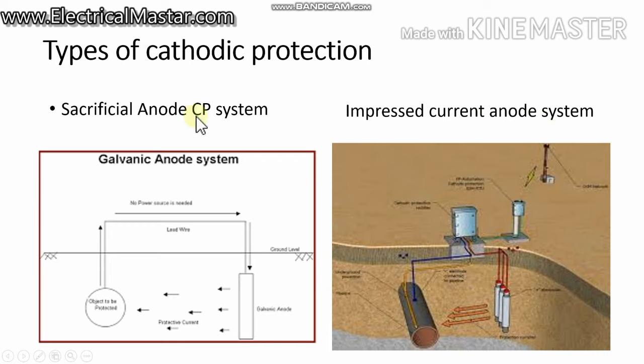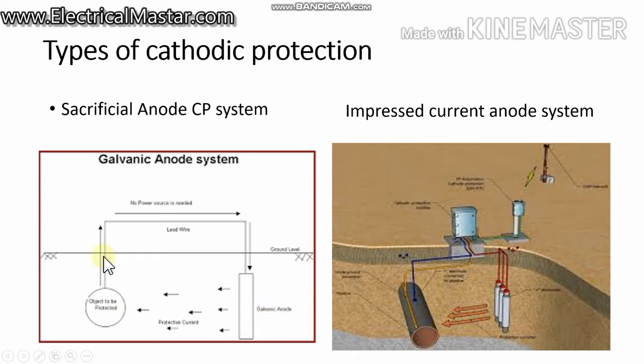The other method is the sacrificial anode system. In this method, there is no external power supply — the anode is simply placed near the pipeline, and the anode and the protected pipeline structure are directly connected through a cable wire. Due to the natural positive property of the anode, current flows from the anode (positive) to the pipeline (negative) and returns back, keeping the pipeline cathodic so it does not corrode. The anode itself gets corroded — it is sacrificed. This is an older method; the impressed current anode system is more efficient and more commonly used.